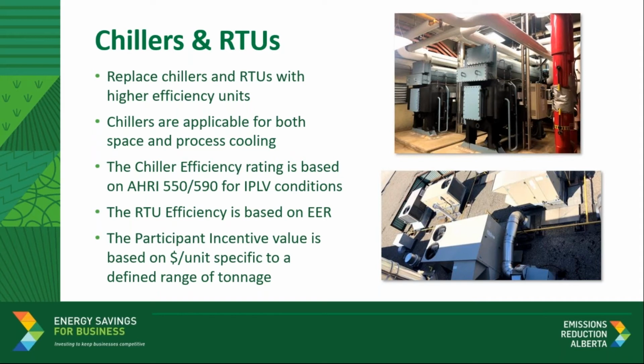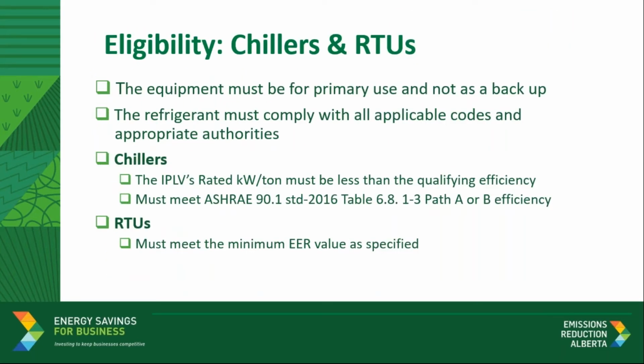Thanks, Surya. Could you take us through the eligibility considerations for chillers and rooftop units? Yeah. So to be eligible for the program, the chillers or rooftop units must be utilized as primary equipment, not as a backup. It is required that the refrigerant in service comply with all the applicable codes and appropriate authorities. In terms of efficiency, it is required that chillers' IPLV-rated kilowatt per ton be less than the qualifying efficiency, and they must meet the relevant ASHRAE 90.1 standard. For rooftop units, they are required to meet the minimum EER value as specified in the eligible measures list.